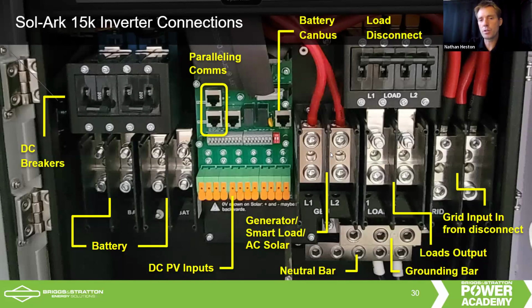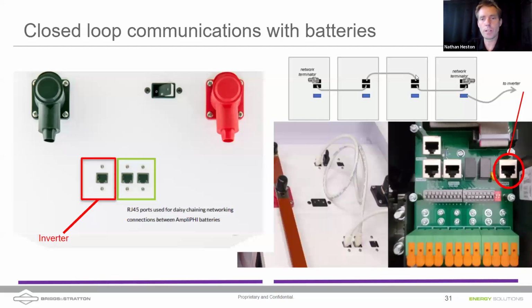Again, there's a nice feature of the generator port on a Sol-Ark 15K: you can use this as a battery state of charge regulated output. So you can put a sub panel on this generator port. Neutral bar and the grounding bar are here on the inverter, and then the load port and the grid port. Now, this is not on the load side of things. That's a load disconnect. It's not a load breaker, so you'll want to use a panel that's got a breaker integrated into it. So let me keep moving forward on the communications.